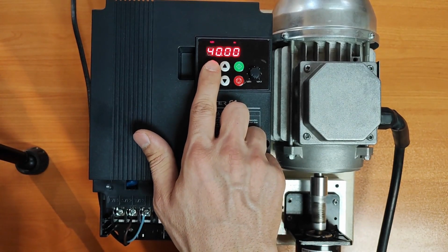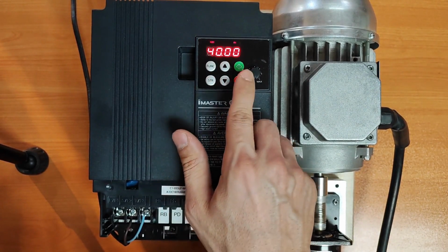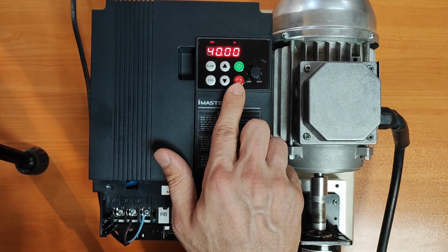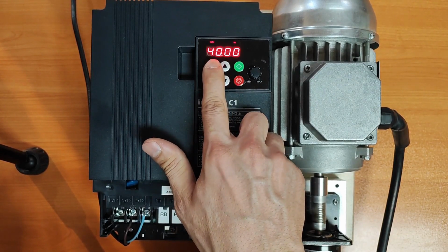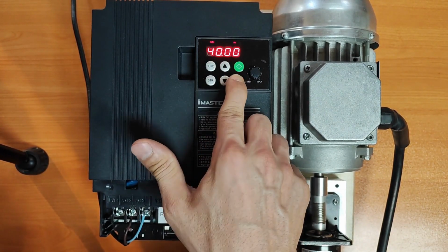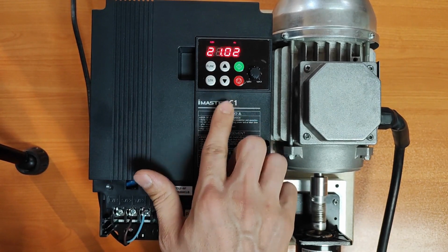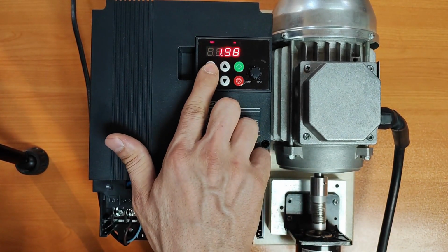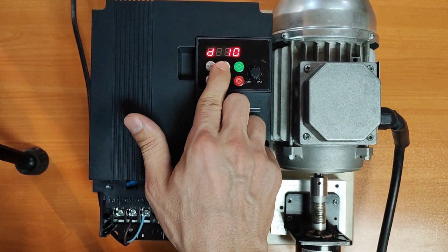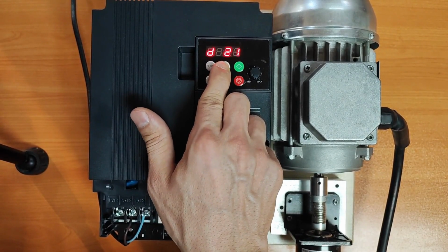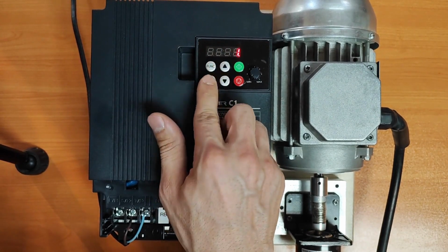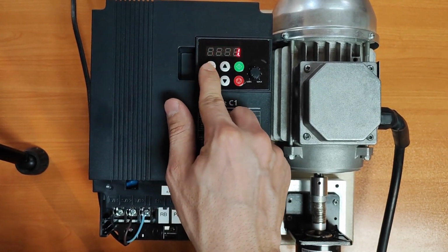Now, if the rotation direction on the C1 inverter, when starting and stopping from the keypad, is opposite to what we want, we can go to parameter 4 in group F to fix this and change the rotation direction. I'll stop the inverter now. The rotation was forward just now. To reverse it, I'm entering parameter group F. In parameter number 4, it's currently at 0. If we set it to 1, the rotation will be reversed. I'll save that.